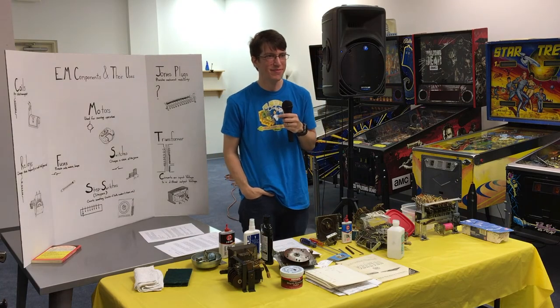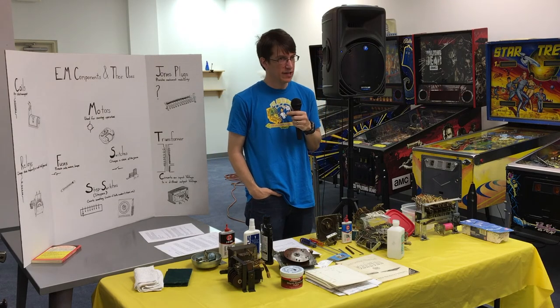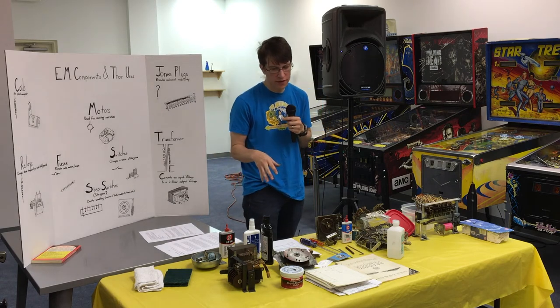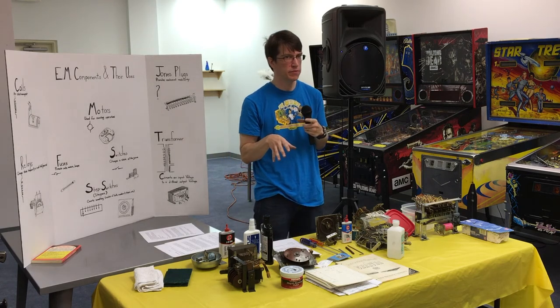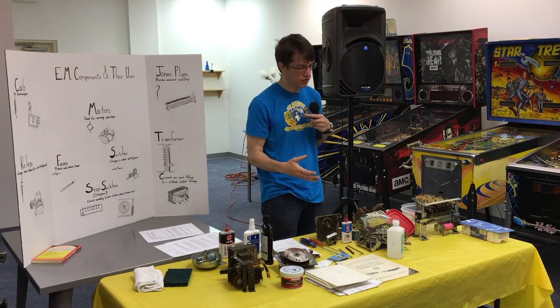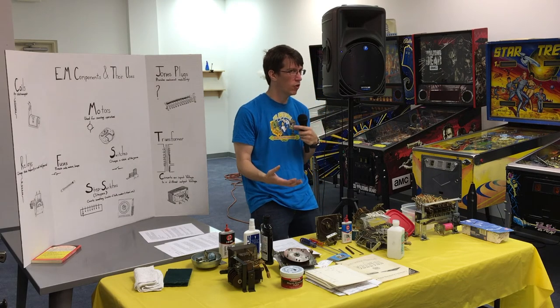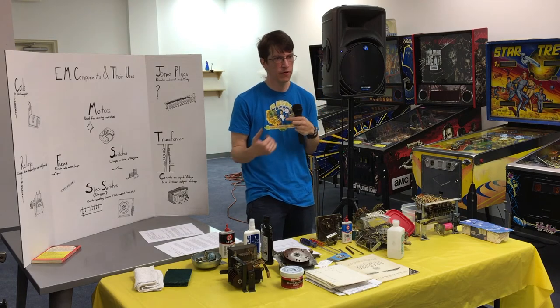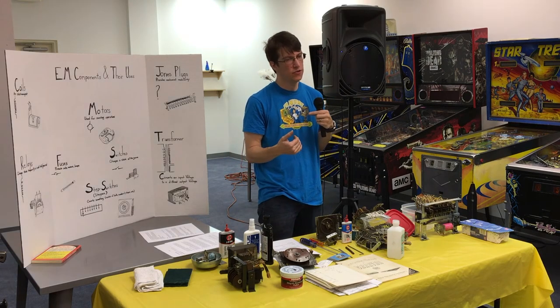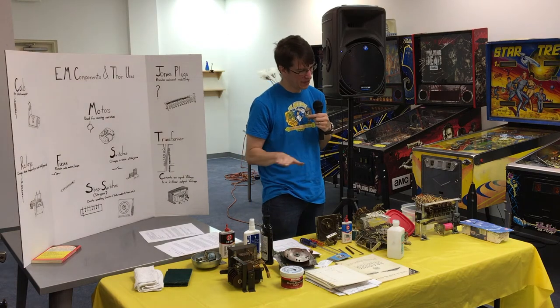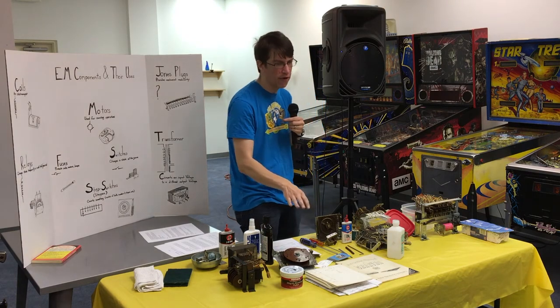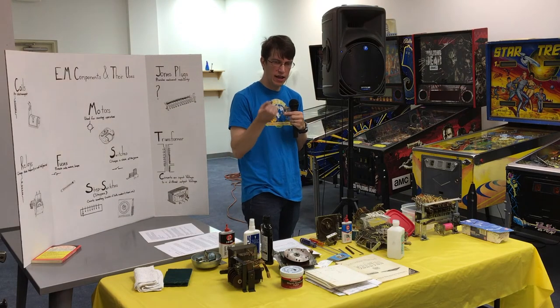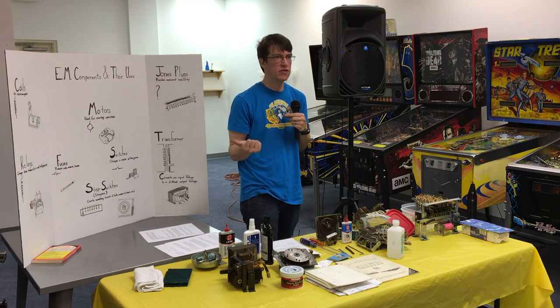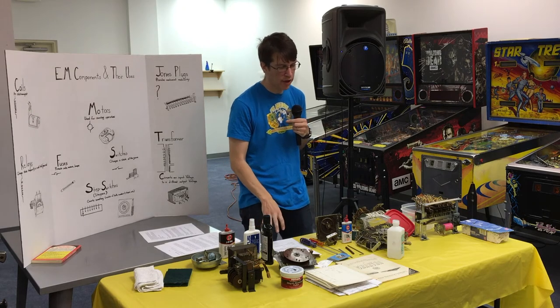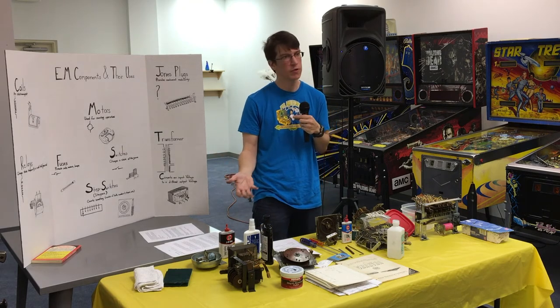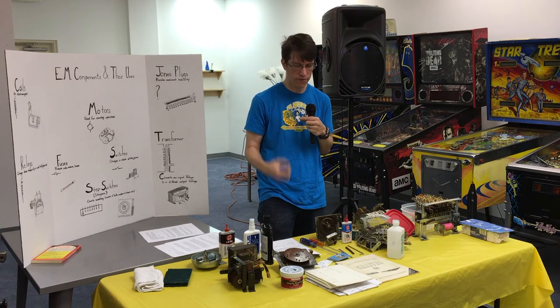Now, are EMs typically fast or slow blow, like a WPC? Typically fast. Now, schematics - we'll get into those in a moment - will be labeled whether it's fast or slow blow. Generally it doesn't matter a whole lot if you substitute a slow blow for a fast blow in an EM, generally, but that's not 100% of the time. Try to follow what the schematic has, that's all that you've got. It's more important to match the amperage than it is to match fast or slow. It'll still blow, it'll just take longer, which means that your components will receive that over current for longer.